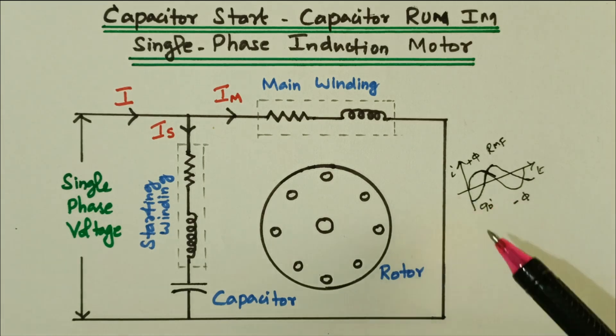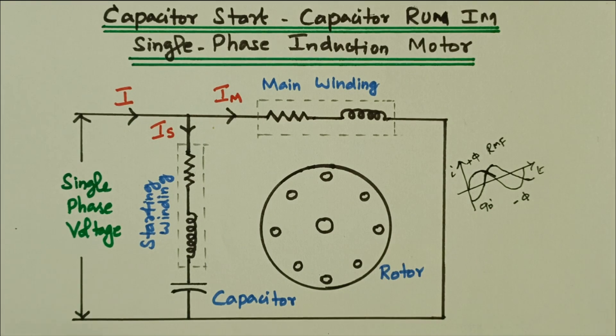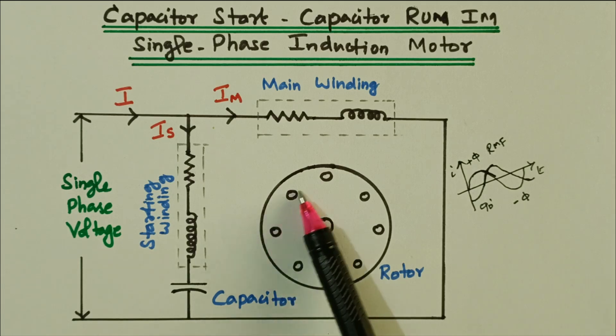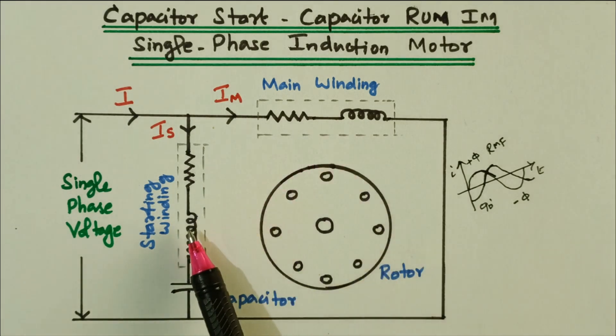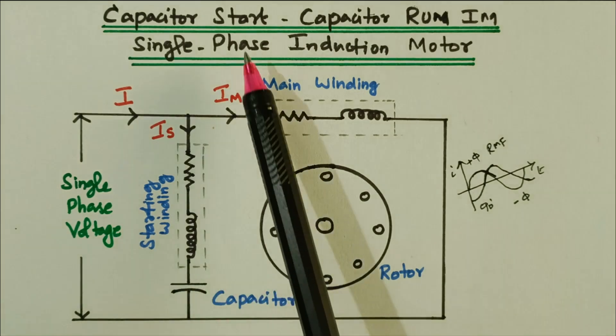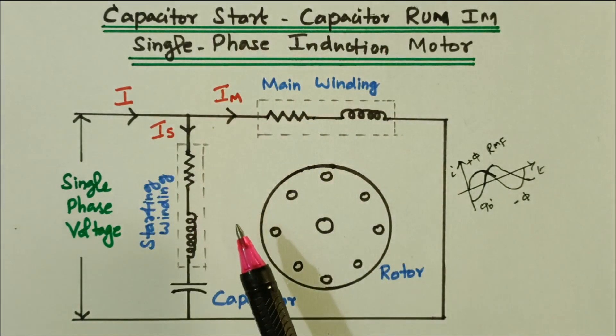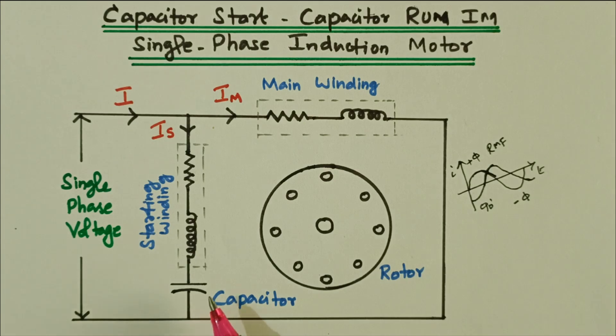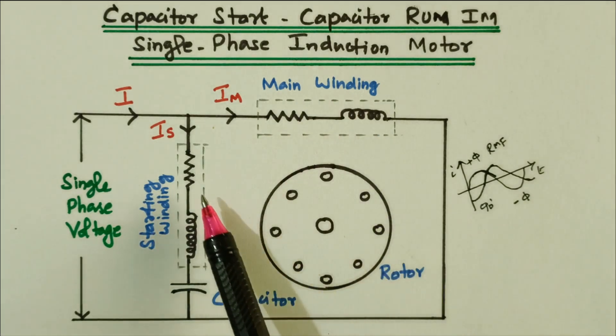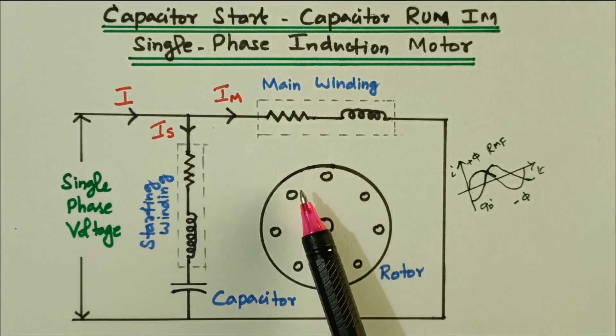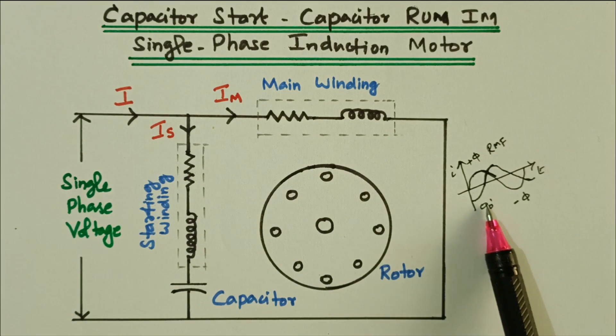Similar to this, we will see the capacitor start capacitor run induction motor. The circuit diagram has a rotor (rotating part) and a stator. We have two windings: main winding and starting winding. In the previous type — capacitor start induction motor — the capacitor is disconnected after the motor reaches running speed. But here we are not disconnecting it, so it is called starting winding and running winding — both remain connected.